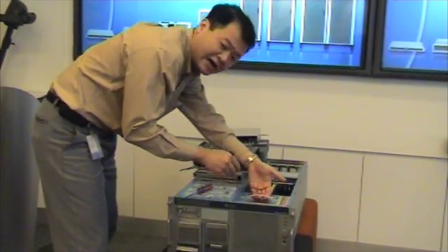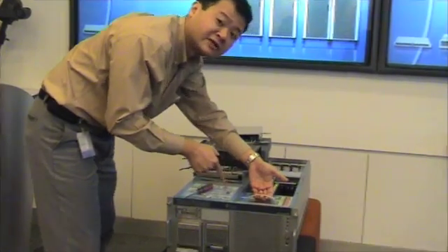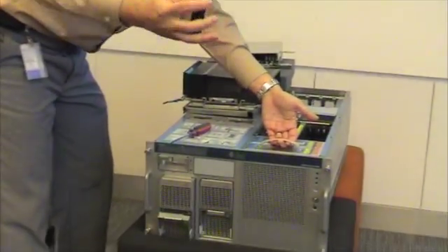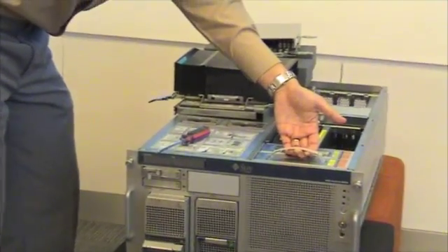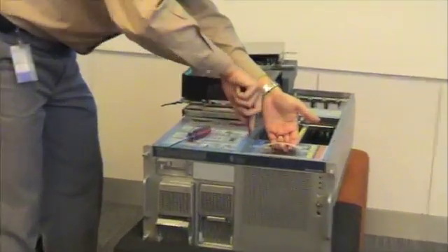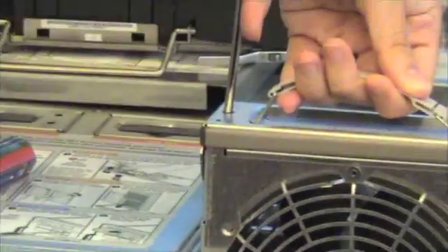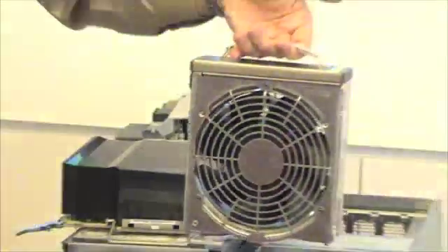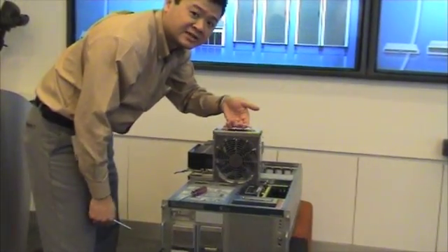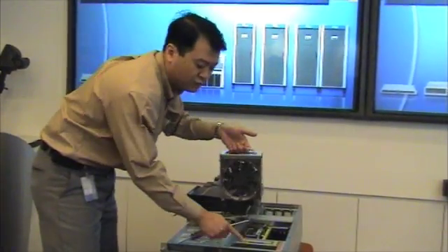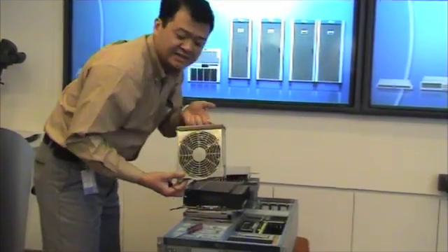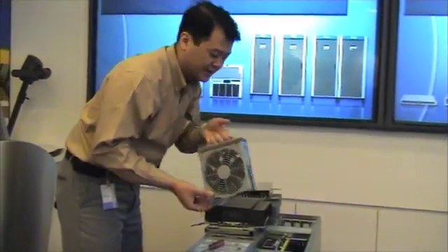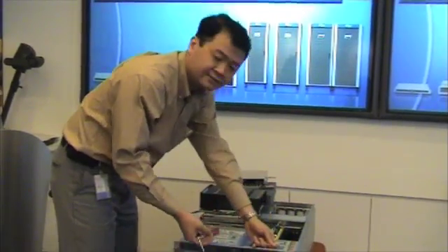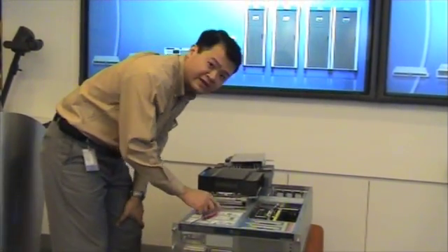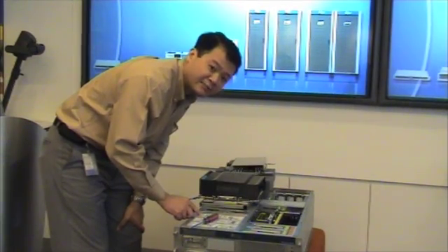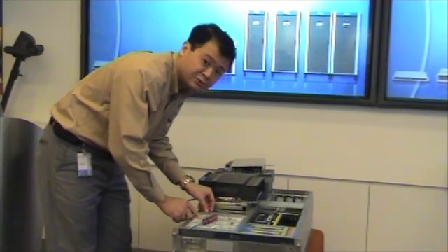Let me just demonstrate how I remove a faulty fan. I'll just use a normal screwdriver with a very sharp pointed nose, press and lift. While the system is running, that is very important, the serviceability of these systems. And we have two of these. So this is a fan replaced, and we can install it back. We have another two fans sitting here. Again, this can be replaced while the system is still running.